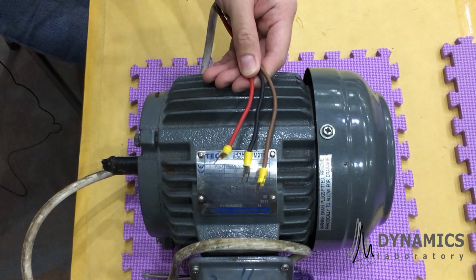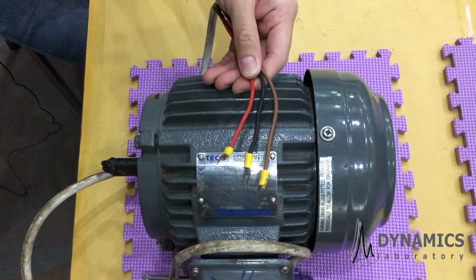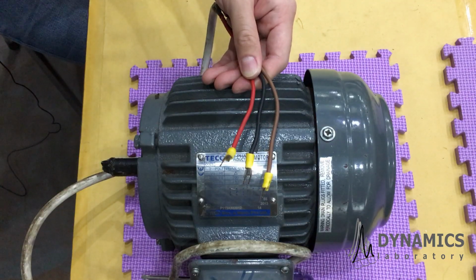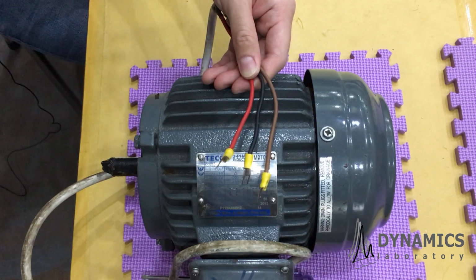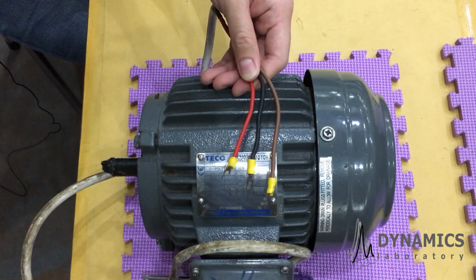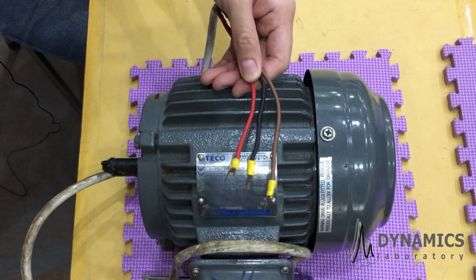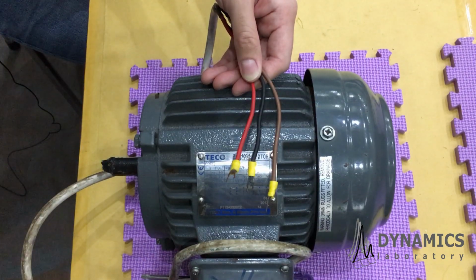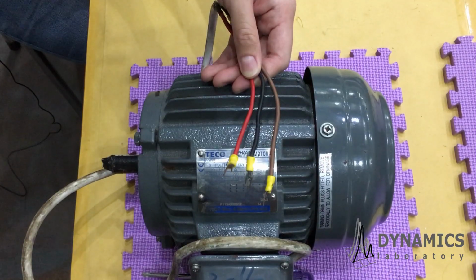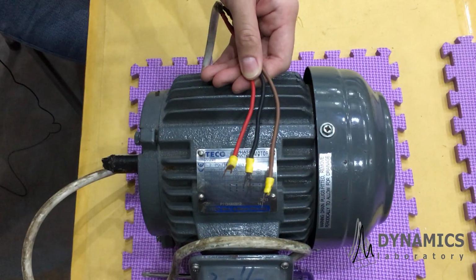How three-phase AC motor works? In three-phase AC motor, we have 3 coils, U, V, and W. Therefore, we should have 6 cables to represent the end of each winding. But in here, we only have 3 cables to represent each winding. Why? Because we have already connected the other cable ends to create Y configuration. Maybe you still don't understand it right now, but it's okay because we will discuss this again in module 4.